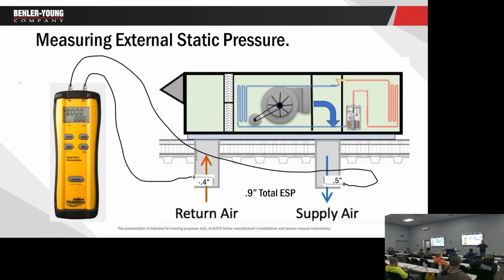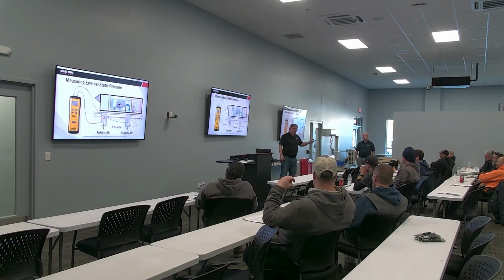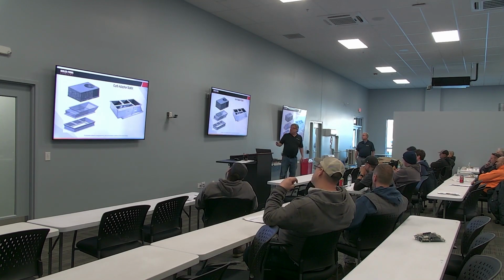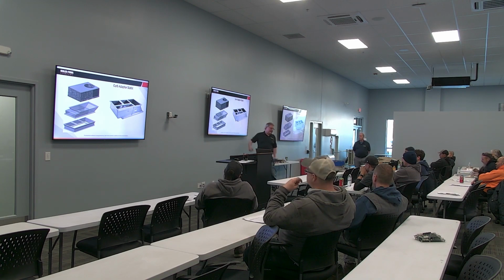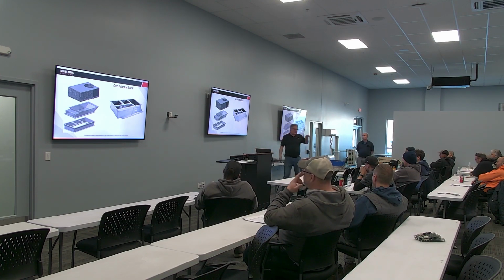So we're not measuring the curb adapter. If we measured up above the curb adapter, we're not going to get correct readings, but we would get the curb adapter. So good point. When you're measuring the ductwork, you're not measuring the curb adapter, you're not measuring in the economizer. That's why we have to add them. Okay, yeah, because we'd be measuring down here, unit be sitting up here, so whatever this is adding, we wouldn't know unless we measure it in the unit, which we can't get an accurate reading in the unit because of turbulence.